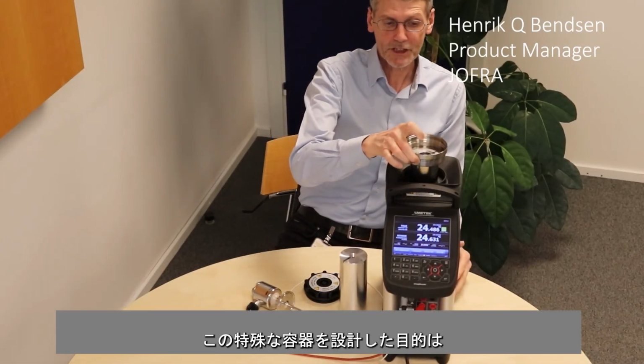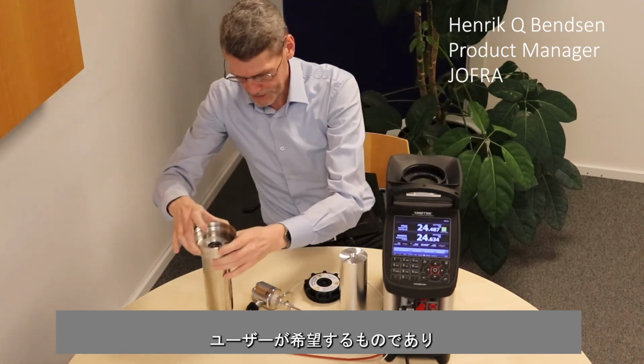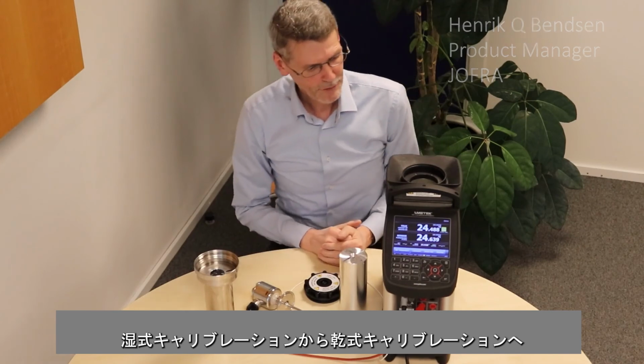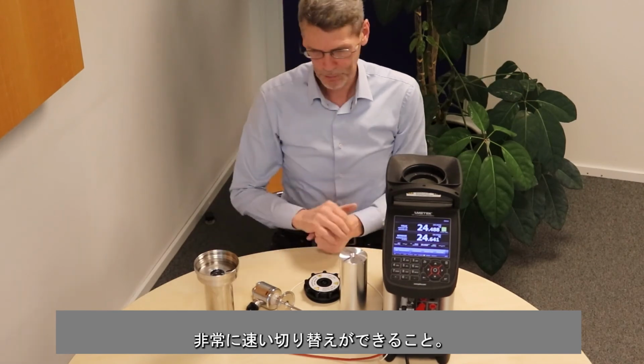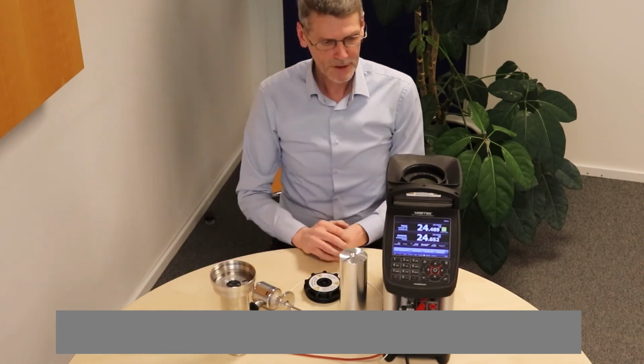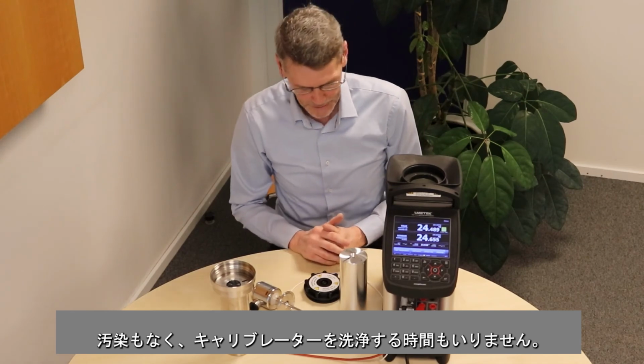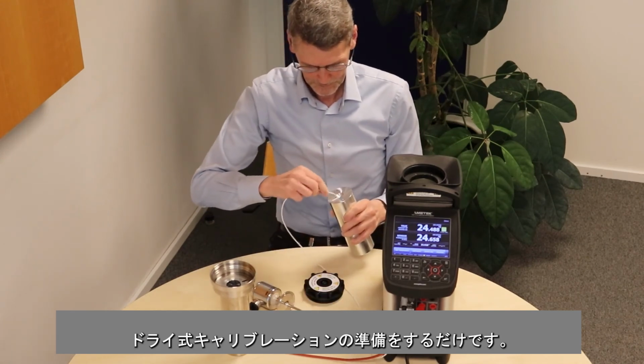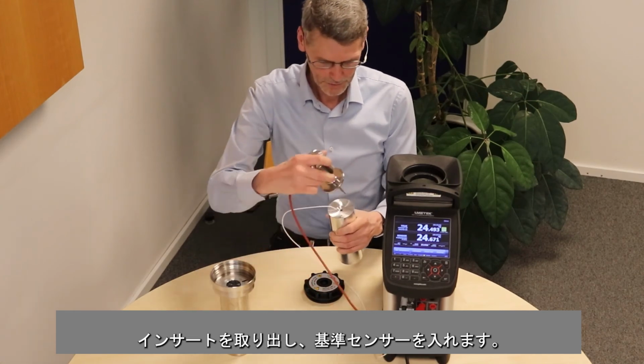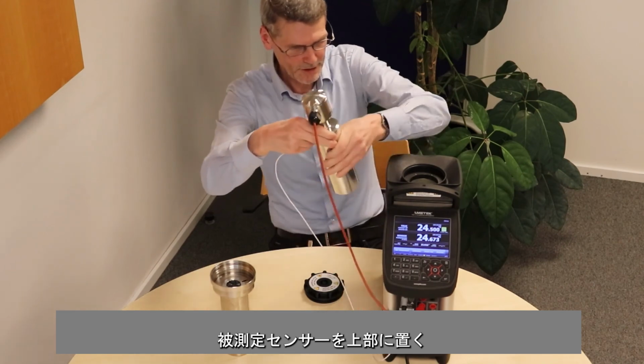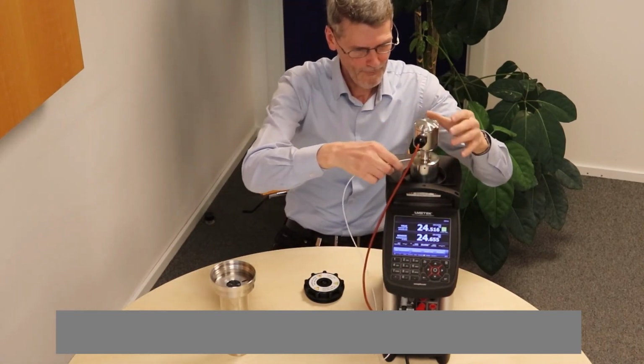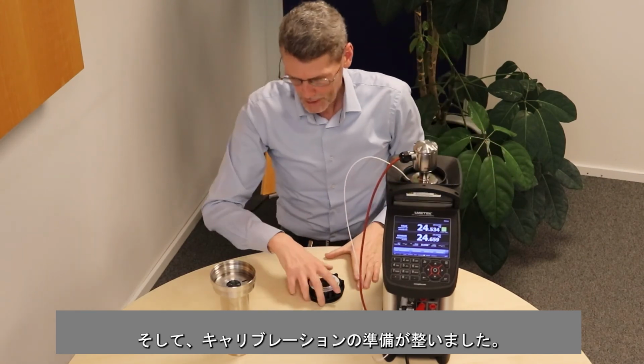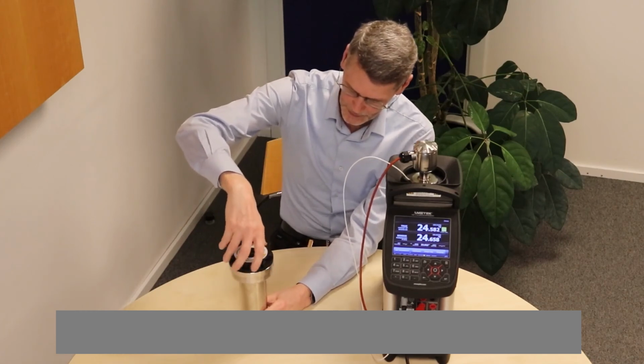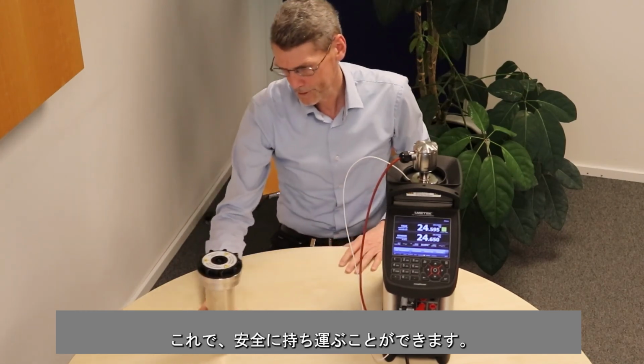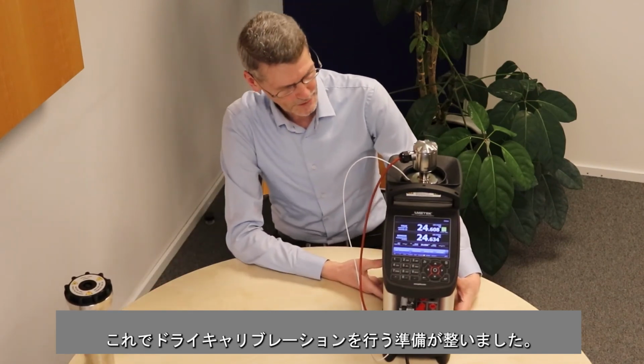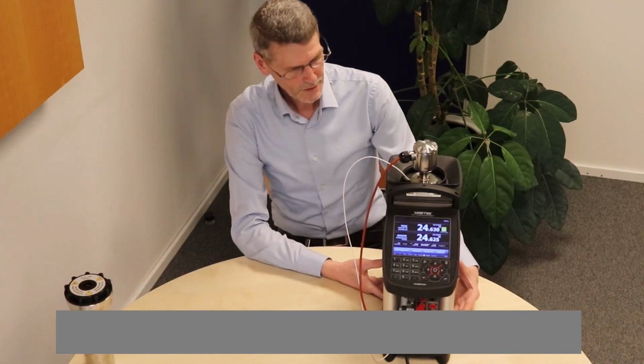The purpose of designing this special container is that our customer wants that we can make a very fast switch from wet to dry calibration. So now we can just take out the wet calibration, no contamination, no time for cleaning the calibrator. Just make ready for the dry calibration. Very simple and easy like that. Take the insert, put in the reference sensor, put the sensor under test on the top, and then we are ready to calibrate. But for safety, we have also made this lid to put on the container, so now we can transport that safely. Now we are ready to do dry calibration. This is the fastest switch you can do from wet to dry calibration.